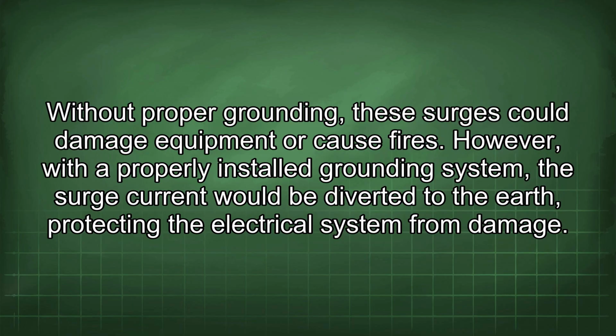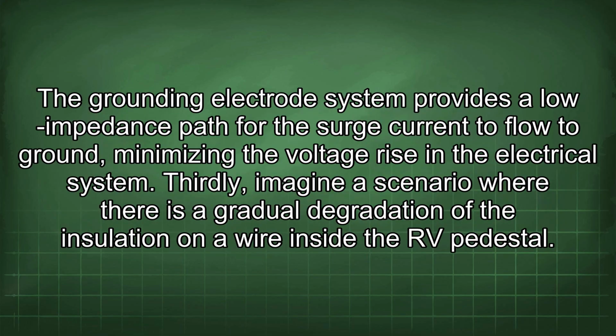Without proper grounding, these surges could damage equipment or cause fires. However, with a properly installed grounding system, the surge current would be diverted to the earth, protecting the electrical system from damage. The grounding electrode system provides a low impedance path for the surge current to flow to ground, minimizing the voltage rise in the electrical system.